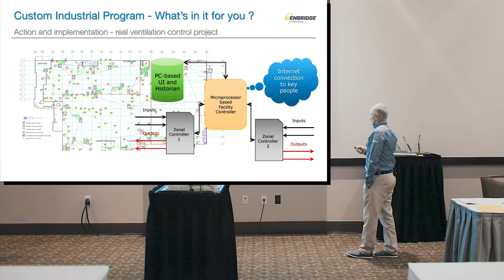So if a unit was operational outside of the scheduled time, he would get a notification on his smartphone saying equipment's running, is that okay? This is what they produced themselves, with their vendor doing the PLC programming. In the end, they set it up on their desktop: ventilation summer schedule running, heating spring/fall schedule running at particular times. They also attached their lighting to the system, so they could control lighting based on which line was operational, since there's no point running all the lights in the facility if they're not needed. He could do all of this from his desktop.